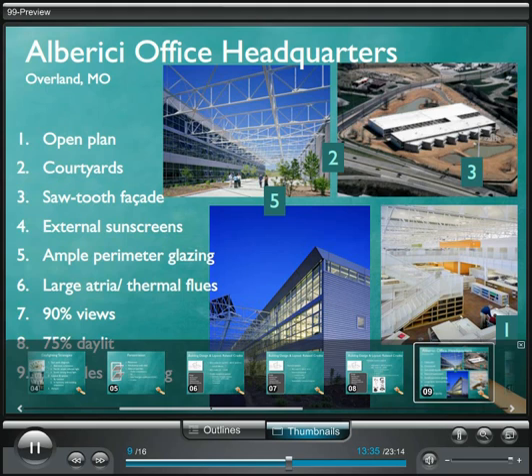The building envelope was designed with ample perimeter and clerestory glazing, so that 75% of all interior spaces are daylit, and 90% of all occupied spaces have views to the outdoors. Three different shades of glazing were chosen to work with various exposures. Working with an existing structure made it impractical to attempt to orient the building itself to the sun path diagram, and the existing structure had a long facade facing southwest. The designers mitigated the potential heat gain from this exposure by extending the facade in a sawtooth shape that blocks western exposure while opening up to the south.